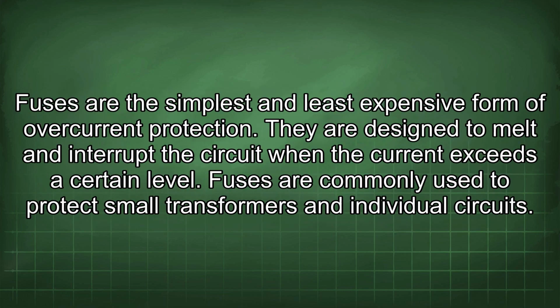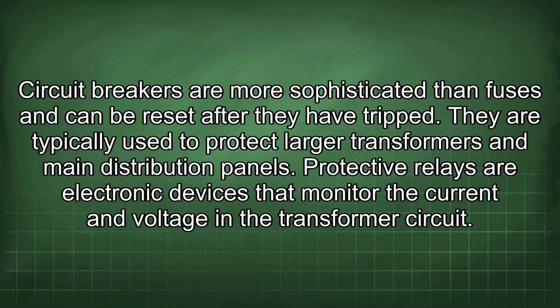Fuses are the simplest and least expensive form of overcurrent protection. They are designed to melt and interrupt the circuit when the current exceeds a certain level. Fuses are commonly used to protect small transformers and individual circuits. Circuit breakers are more sophisticated than fuses and can be reset after they have tripped. They are typically used to protect larger transformers and main distribution panels.